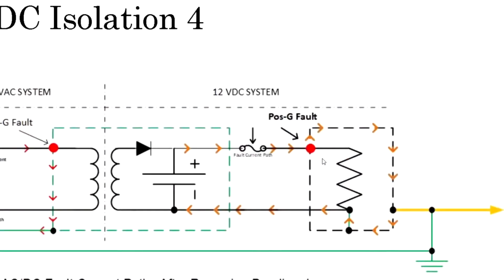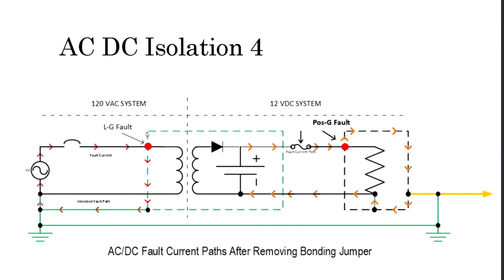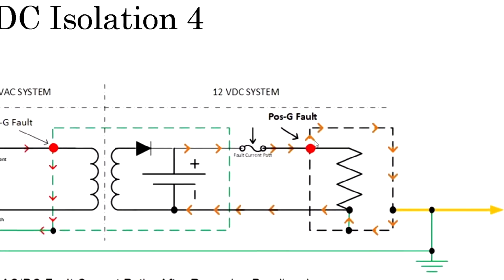Okay, wrapping up AC-DC isolation here, I've induced two faults to see how it all works. So on the left, we've got an AC fault, line to ground or line to chassis. It returns straight back to the utility's neutral through the equipment grounding conductor that ran with the house wiring circuit. The DC side, if we have a DC fault, it's contained right here. It's returned right back to the DC power plant, the source of the power.